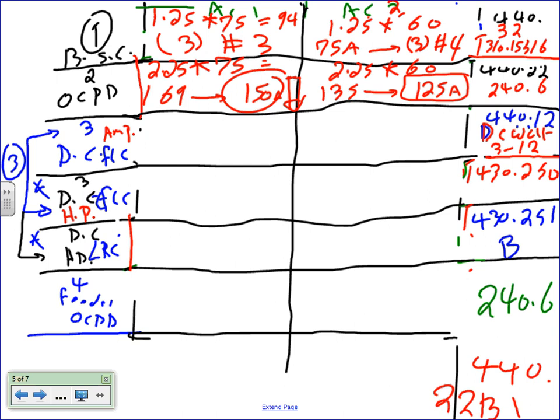Okay. So you can go up to 2.25 if you know the equipment is not going to start with 1.75. If you read through it. Yeah, so it's up to you guys where you put your start point. Can I admit one little thing? These guys will be sized by the manufacturers anyway. Remember how we said this is a maximum overcurrent protection device that's sized by the manufacturer. So you're going to find it sized by the manufacturer anyway. But for the sake of knowing how, for the test, size it, boys, on 2.25.